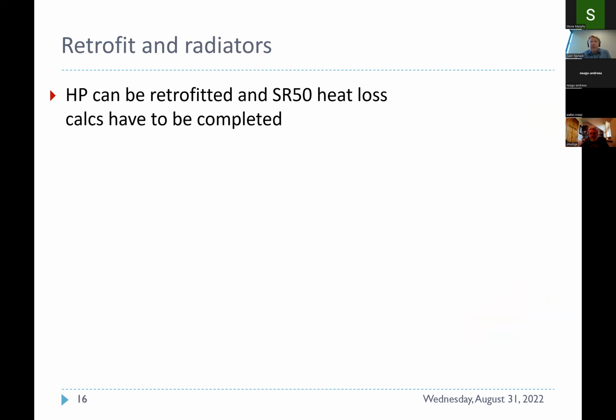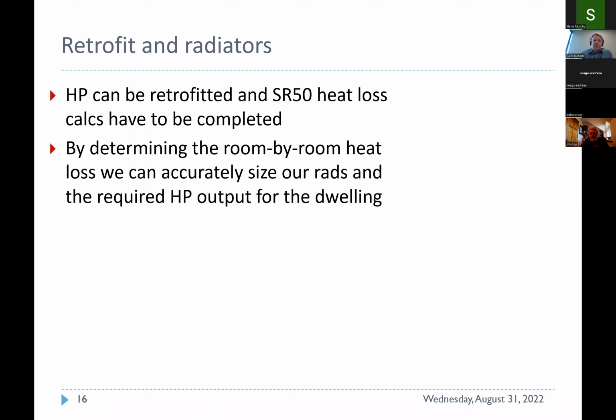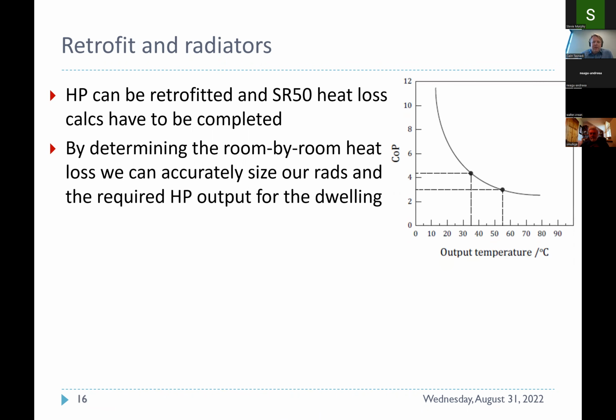Retrofit, obviously everybody's talking about retrofit and the issues that we may or may not have, but it's very important that we have SR50 heat loss calculations done to ensure that the radiators are sized accordingly in a room-by-room scenario, so we can then determine the required heat pump output for the dwelling and for the radiators at various delta T's. I'm bringing this up again just to show you that it is important to keep that design temperature as low as possible to get as big an efficiency as possible.